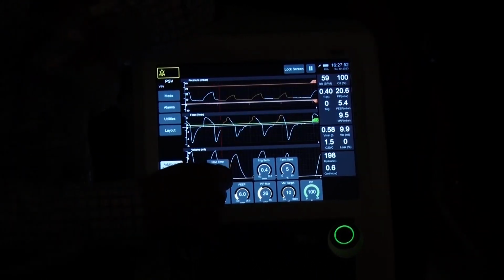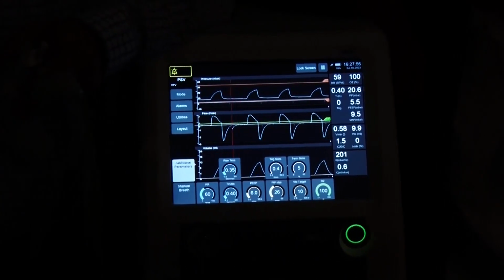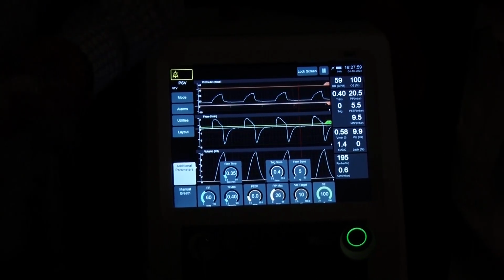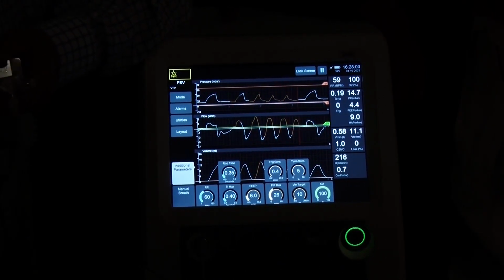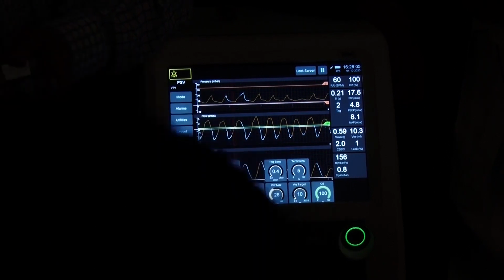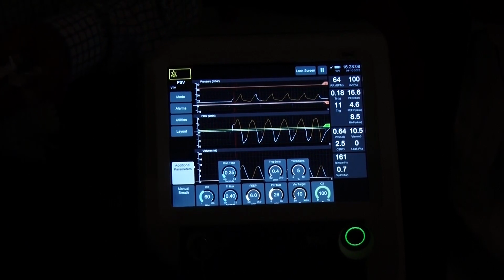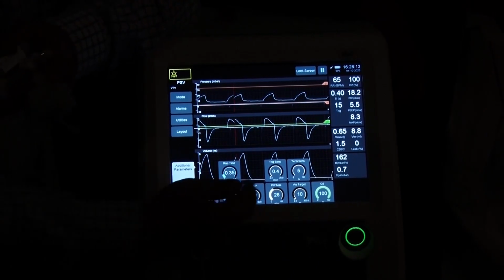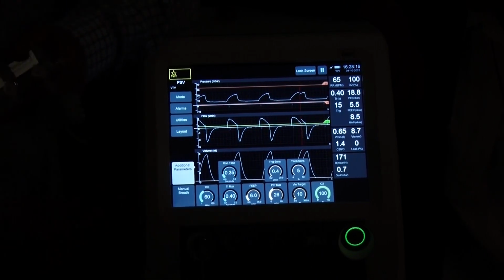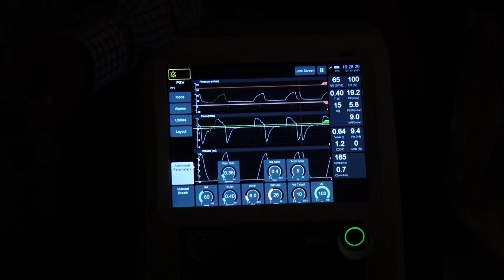But in pressure support, what you're now doing is you're also asking it to trigger expiration, aren't you? So here, if I breathe really fast, it will start to decrease the I time, which you can see on the ventilator here. The I time's changing. And then when I go to apnea, you can see it's going back to just that fixed 0.4, the maximum I time. And you set a maximum one to stop the baby holding their breath forever, right?